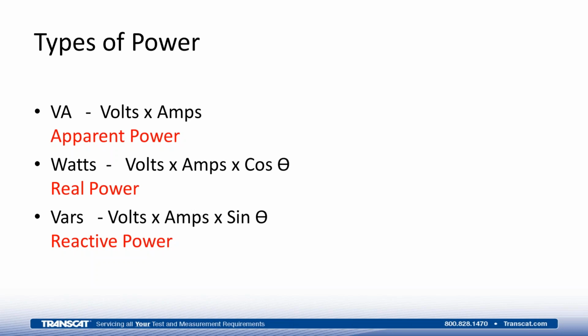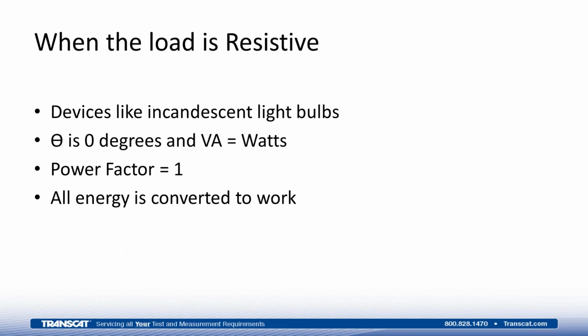And to calculate the VARs, we use the volts times the amps times the sine of theta, the angle between the voltage and the current, or the power factor of the system, and that would give us our VAR loading. You don't need to know these particular things to monitor energy usage, but it does demonstrate that we have to monitor the energy in different ways, depending on whether we are monitoring something that is called a resistive load or something that is not a resistive load.